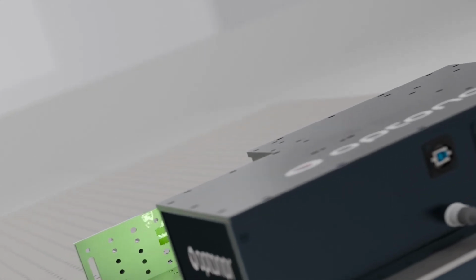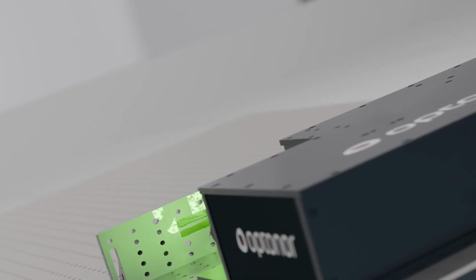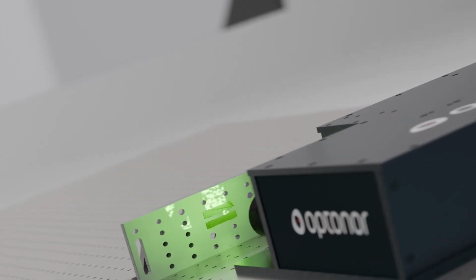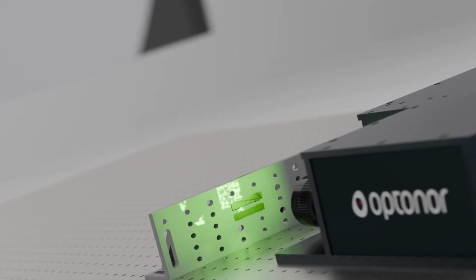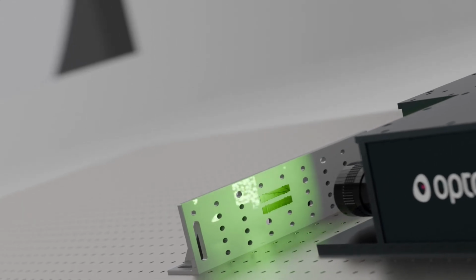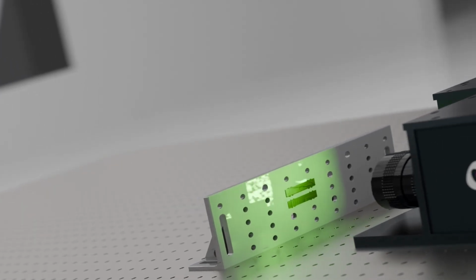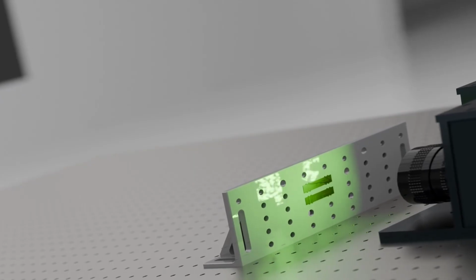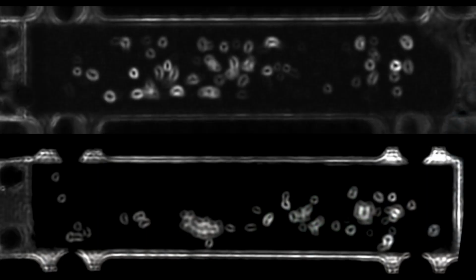In this VibroMap application example, we will take a look at two thin, polymer-coated, single-stack piezoelectric transducers from two different production batches side by side. Our client Norbit wanted to know if the production process at their production facility had improved, and if so, we should see a difference in performance between the older sample at the top and the newer sample at the bottom. First, we run both samples through our patented damage detection scan routine.